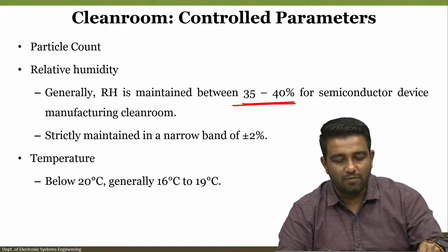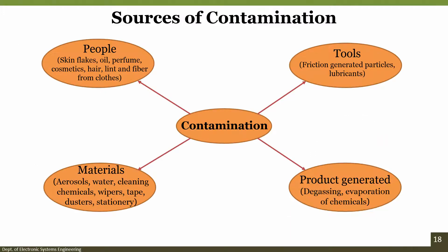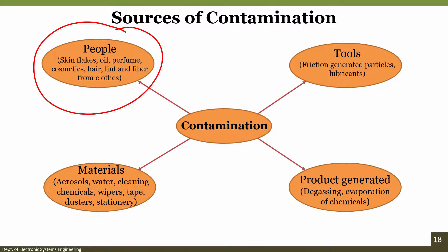There are several sources of contamination, and the biggest is the person working inside the clean room. Contamination comes from materials used inside such as aerosols, water, cleaning chemicals, wipers, tape, dusters, and stationery. It can also come from degassing, evaporation of chemicals at wet benches, and physical vapor deposition like sputtering, e-beam, and thermal evaporation. Tools can generate contamination through friction, lubricants, and particles. People working inside contribute through oil, perfume, cosmetics, hair, lint, and fiber from clothes.